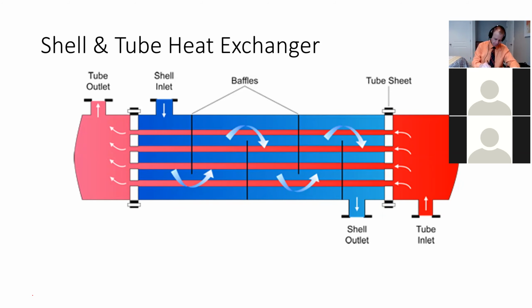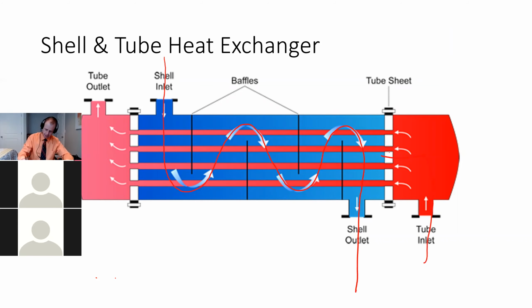And so you can see the shell fluid comes in and it goes back and forth around the baffles, and then it would come out the other side. So here would be a shell inlet, here would be a shell outlet. And you can choose which one's inlet and outlet. And then the tube side, you can see this is called the bonnet, the thing that you screw your entrance pipe into. And then this one, we took the bonnet off so you can see the tube bundle. Then it just comes through, and let me move this real quick. It comes through, the tube inlet goes through all the tubes and then comes out.